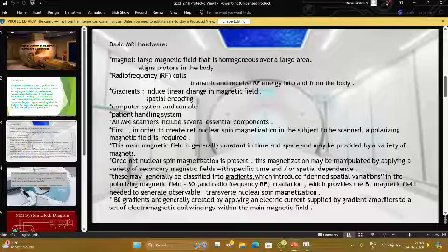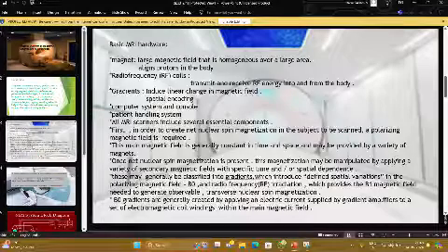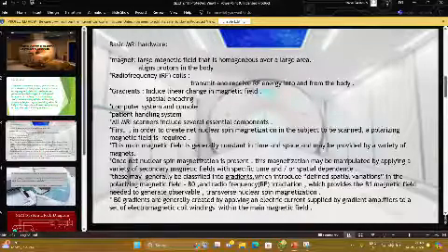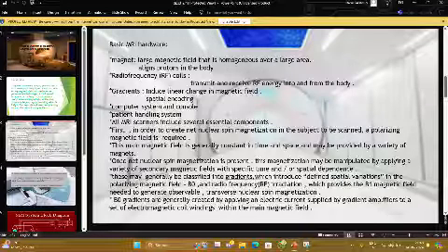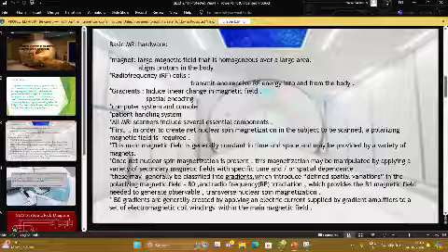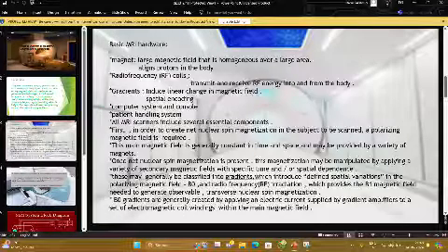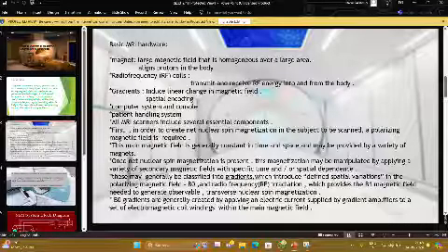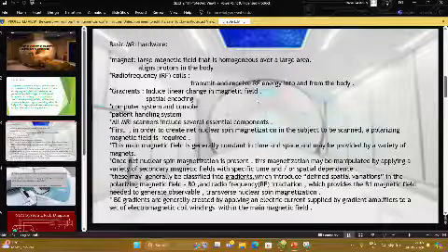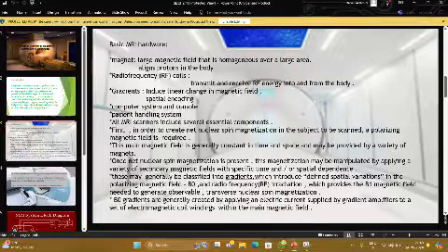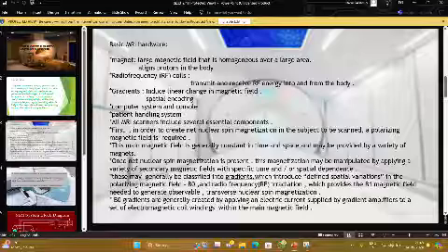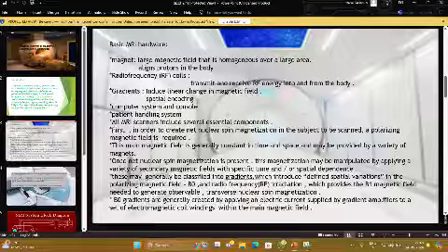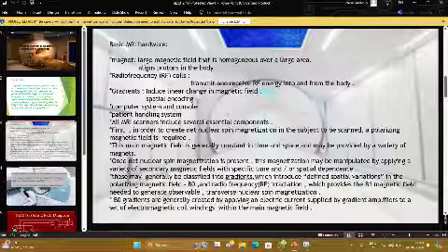Firstly, talking about the basic MRI hardware, the first thing is the magnet. The magnet is a large magnetic field that is homogeneous over a large area and aligns protons in the body. Then radio frequency, RF, coils. These coils transmit and receive RF energy into and from the body. Gradients induce a linear change in magnetic field for spatial encoding. And we also have the computer system and console, then the patient handling system. All MRI scanners include several essential components.